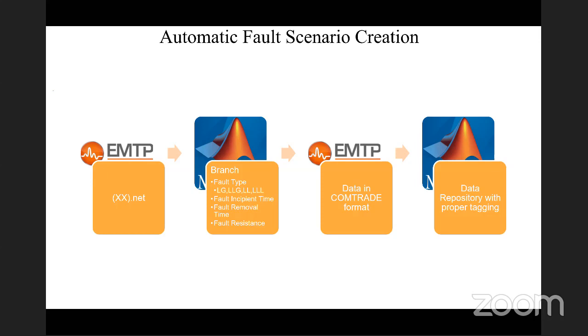If somebody has experience using EMTP-RV and wants to do 2,000 to 3,000 cases, I'm telling you it takes forever, turning on, turning off, fault at this point, fault at another point, fault for 5 milliseconds or 20 milliseconds, 5 cycles duration, fault with different resistance components, single line to ground fault, double line to ground fault, so many things to create. On top of that, you need to create harmonic events. Now if you want to do that automatically, some framework has to be available.